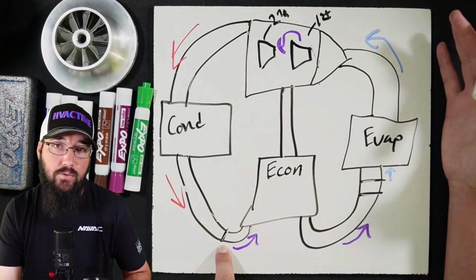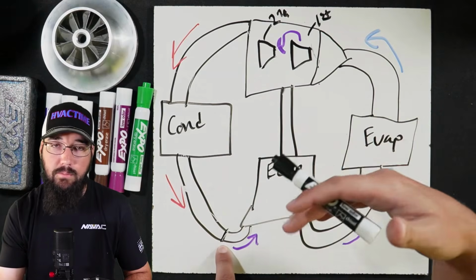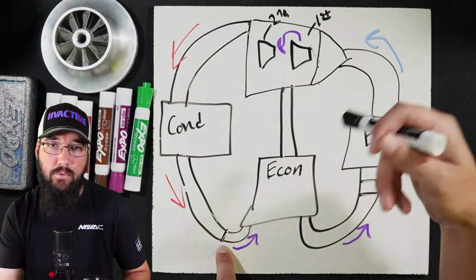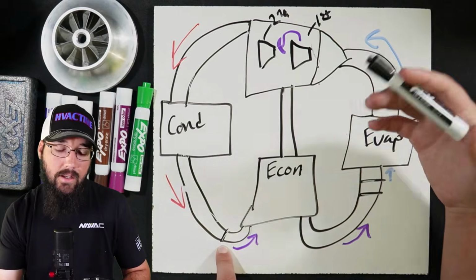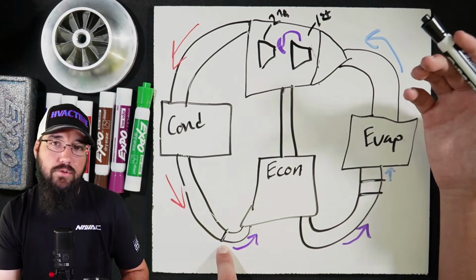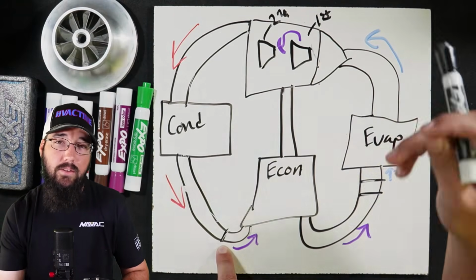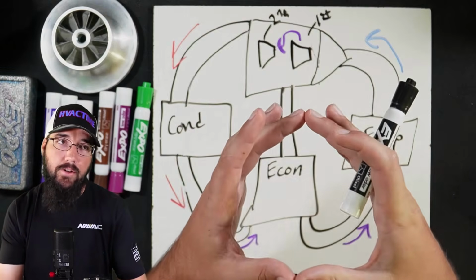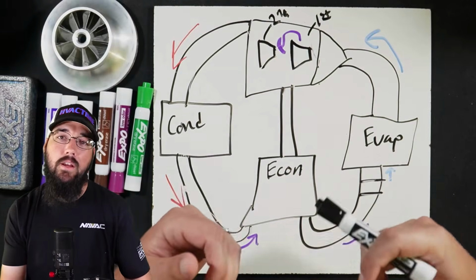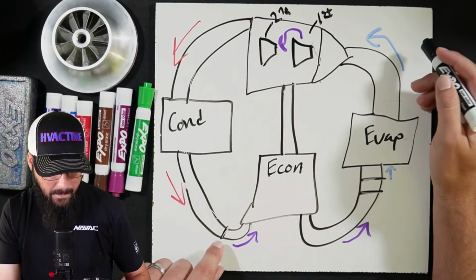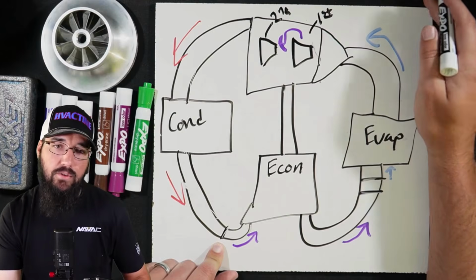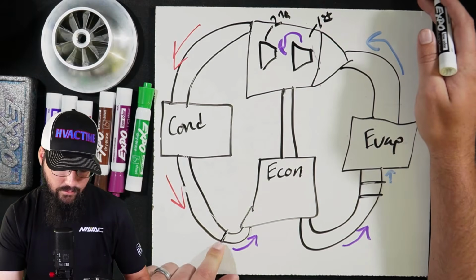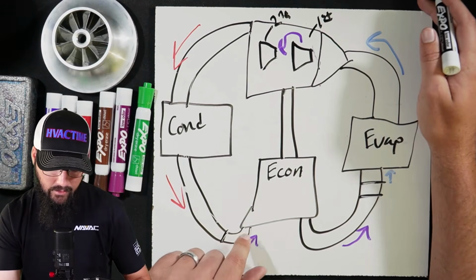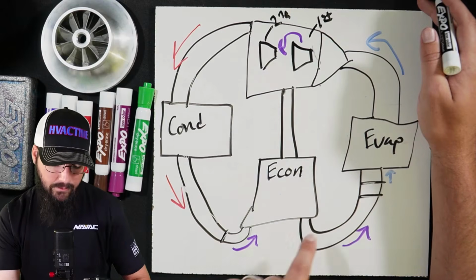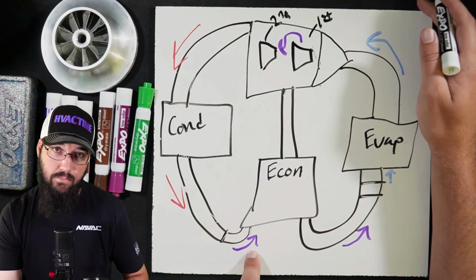It's just a fixed orifice, all right? Just like with a little split system heat pump with a little orifice in there. This is just that on a much larger scale. It's actually a perforated plate, just one steel plate with a bunch of tiny little measured, engineered pinholes in it that creates a pressure drop for us. But once we go through this first stage of pressure drop, we're not actually going into a low pressure state that the evaporator needs. We're going into a medium pressure.